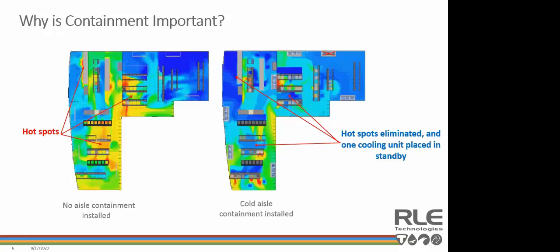Thanks, Tim. So data centers are typically cooled to control the hottest spot in the room. This usually results in overcooling of the entire space to control just a few hot spots. This image shows a real-world example of a data center with no containment compared to a cold aisle containment. This CFD model on the left shows a data center without any aisle containment in place whatsoever.